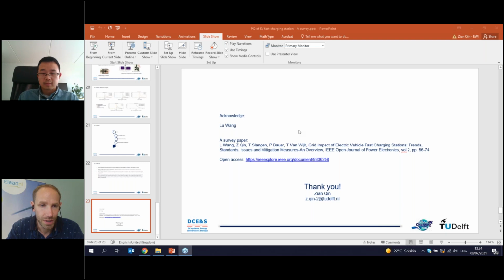Another question from Paul Broos: for fast charging, the power builds up rapidly. Yesterday, a person from the CPO Allego, Martin Jaspers, mentioned that the MV-LV transformers DSOs normally use are not suitable for big load variations. What impact may this have on power quality on the grid? I'd say the major effect, if you're talking about the ramp up, is mainly the flicker, because there is only one ramp up during one charging event, right?